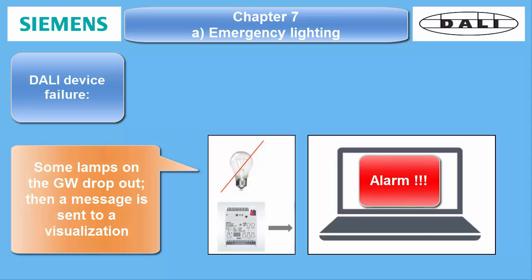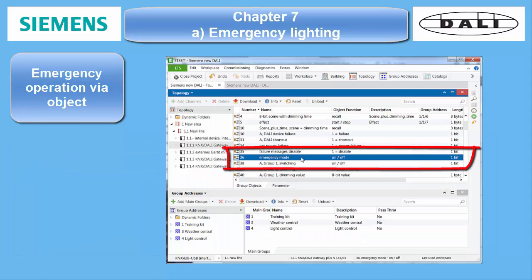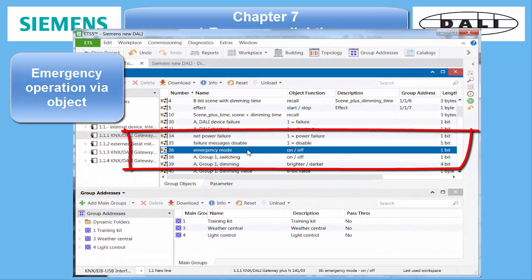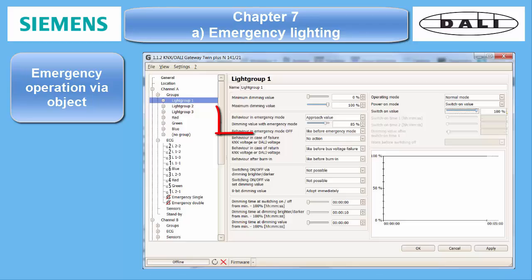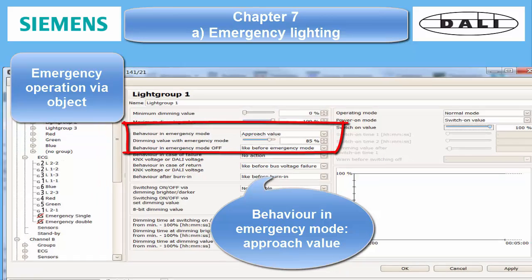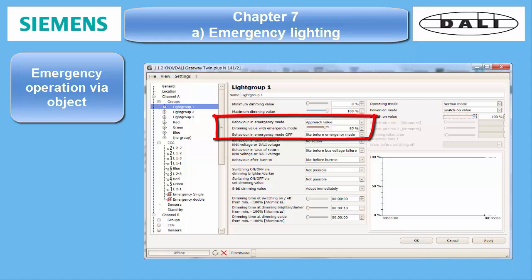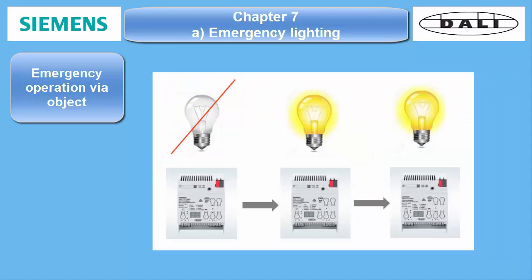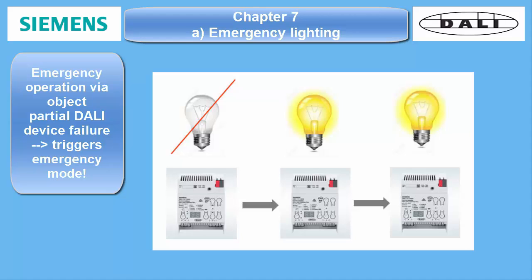Emergency operation and synchronization. All Siemens DALI gateways possess a central communication object: Emergency operation, number 36. Together with the parameter setting of either groups or ECG behavior in emergency mode, it is possible to set all emergency luminaires into a certain emergency operation level at the same time. As a use case, the partial device failure message can be used to trigger this object.